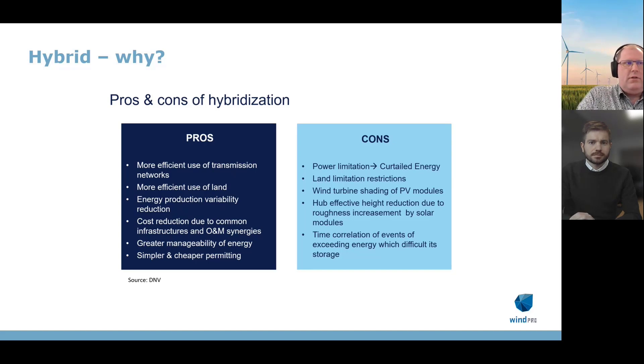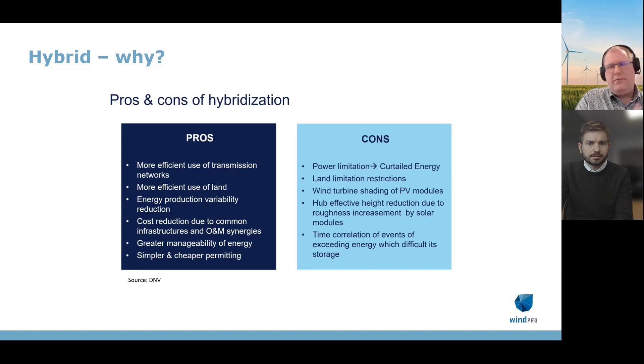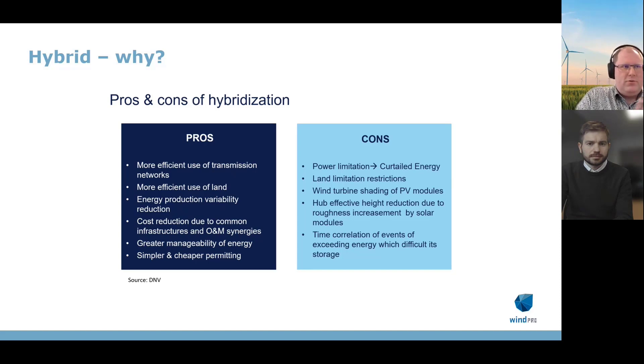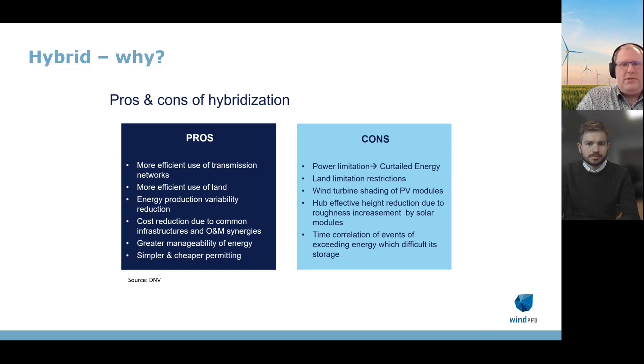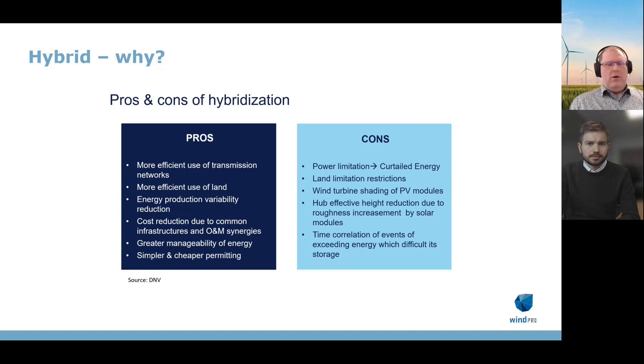There are, of course, also cons. You need to curtail the wind farm or the PV plant in some situations — when you reach the grid capacity limit, you need to curtail. The entire investigation and optimization aims to minimize the value of that curtailment. Quite often we see curtailment in high wind periods, and in high wind periods we often see very low electricity prices. Therefore, curtailment might not mean that much in terms of economy — that's the whole idea: we have very low price hours where we can curtail the wind turbines.